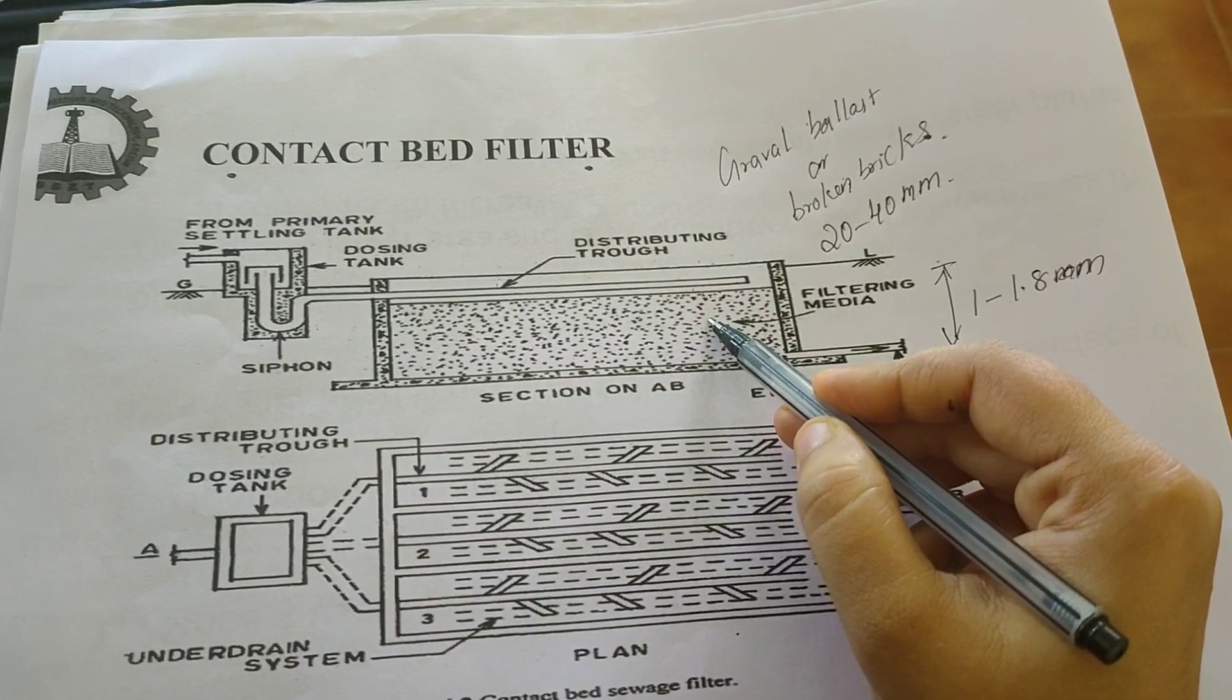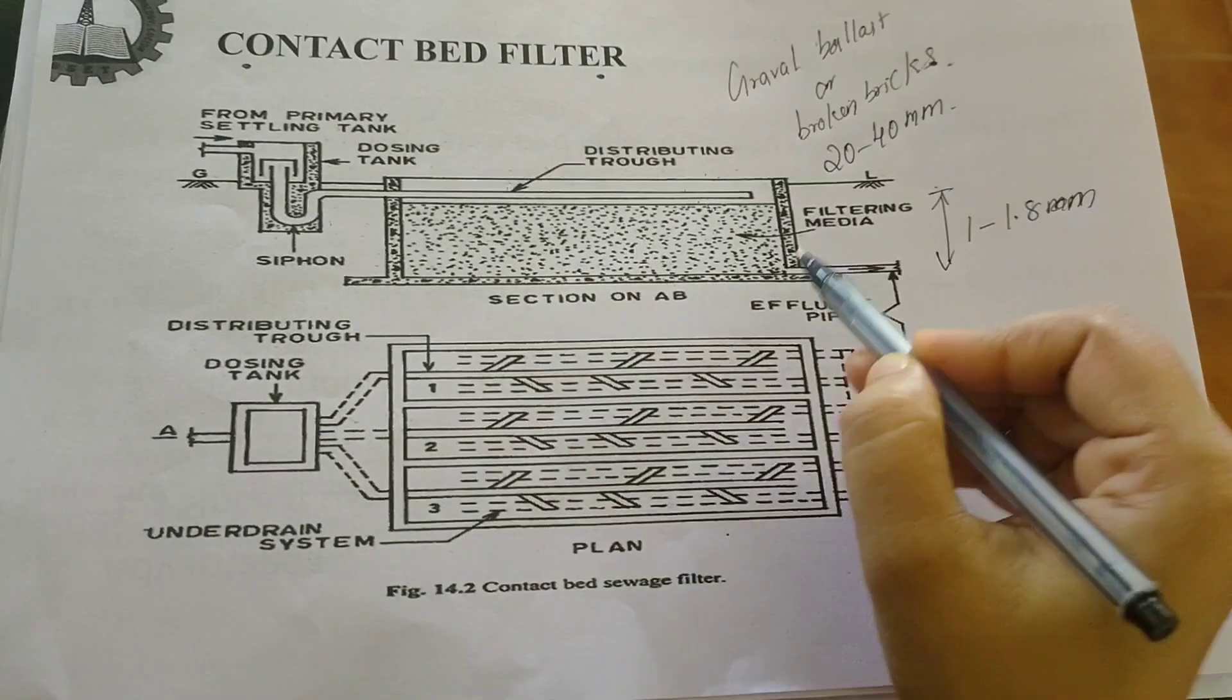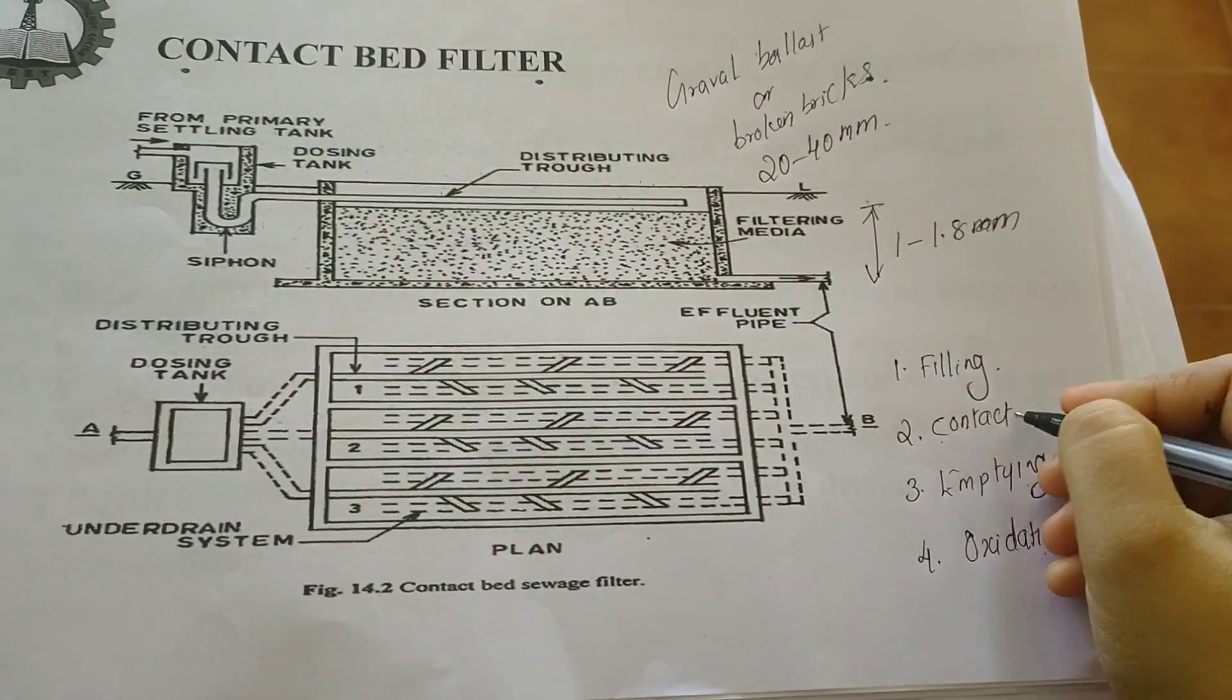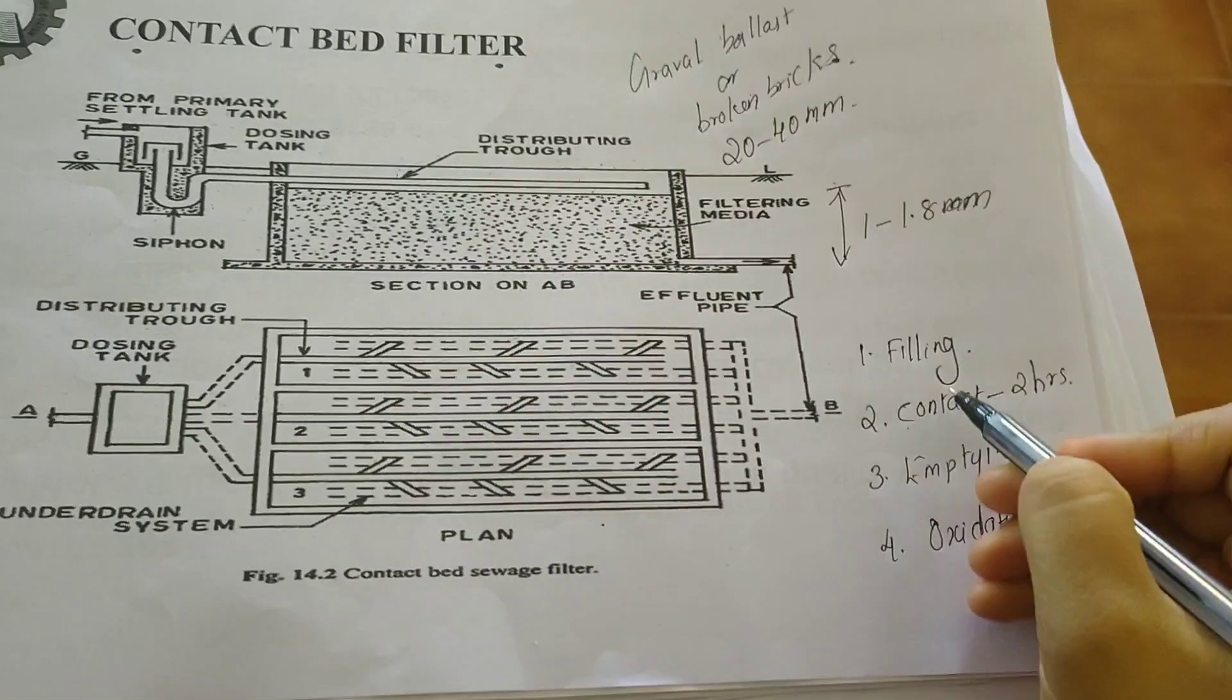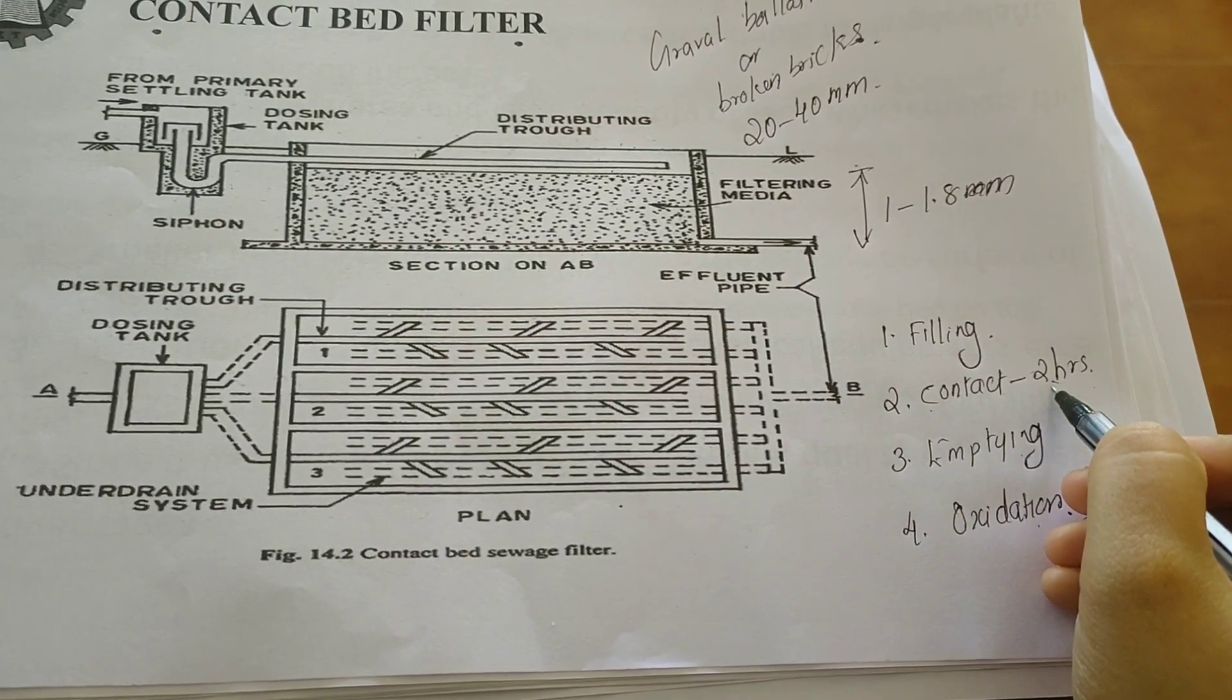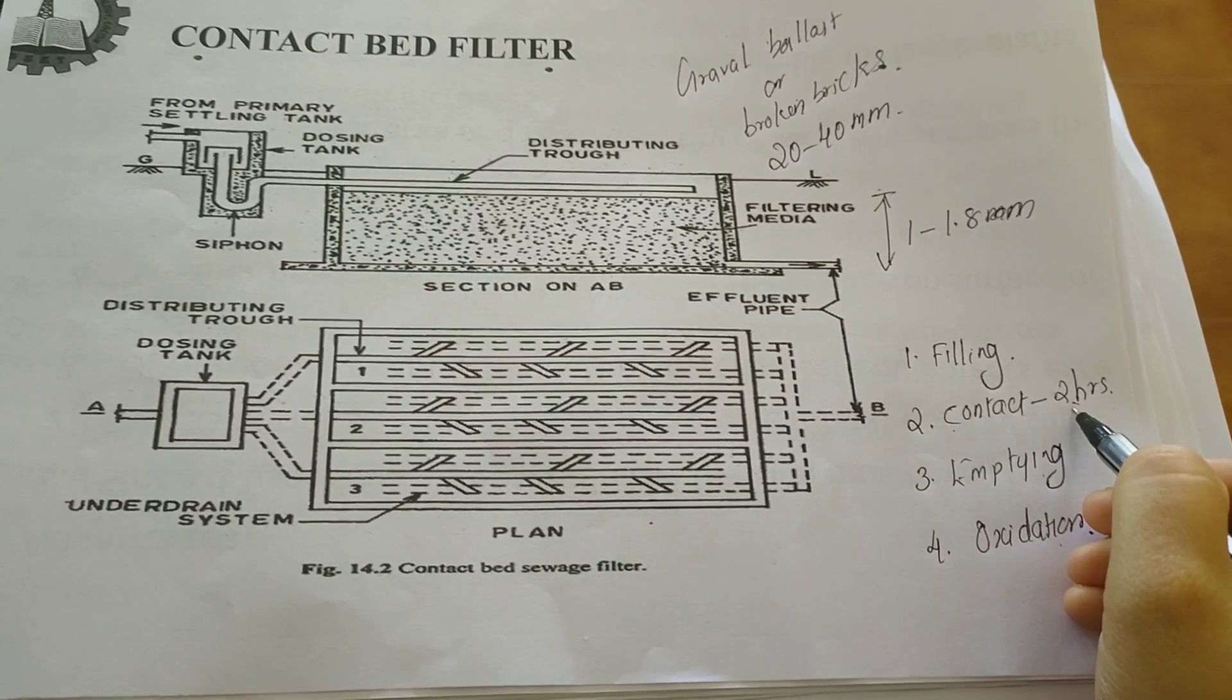Now the second phase is the contact period. In this period the dosing tank will be closed. The sewage will stand for about 2 hours, and these hours are known as the first contact period. In this period the colloidal and dissolved matter gets transferred to the filter media and be in contact with bacterial film.